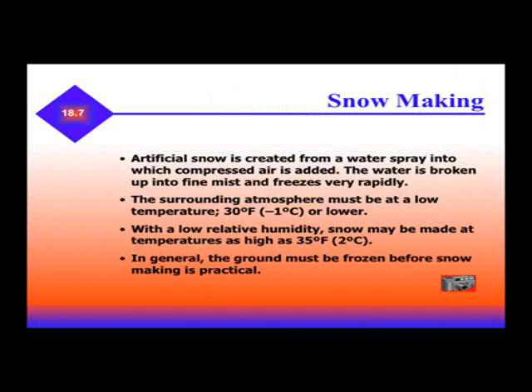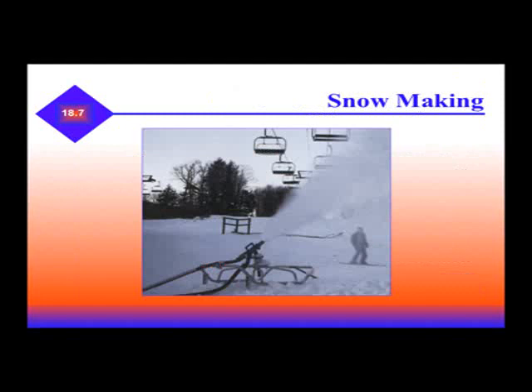Another type of refrigeration system is snow making. Artificial snow is created from a water spray into which compressed air is added. The water is broken up into a fine mist and freezes rapidly. The surrounding atmosphere must be at a low temperature, 30 degrees or lower. With a low relative humidity, snow may be made at temperatures as high as 35 degrees Fahrenheit. In general, the ground must be frozen before snow making is practical. This is an example of a snow making machine on a ski slope.